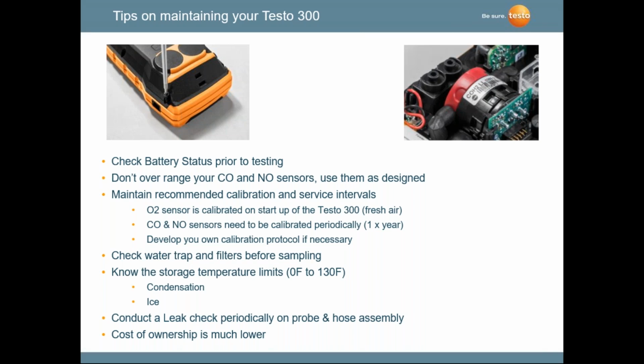Calibration of your electrochemical CO and NO sensors is periodically required. Testo recommends once a year. Send the instrument back to us. We keep track and can calibrate these and put a sticker on to make sure you understand that they've been calibrated, with a certificate. You may have your own calibration protocol, so you may want to do this more frequently than what we recommend. That's up to you.